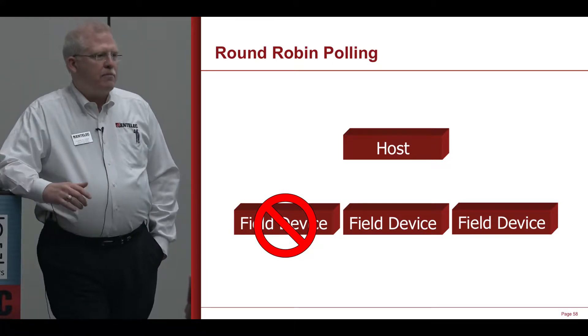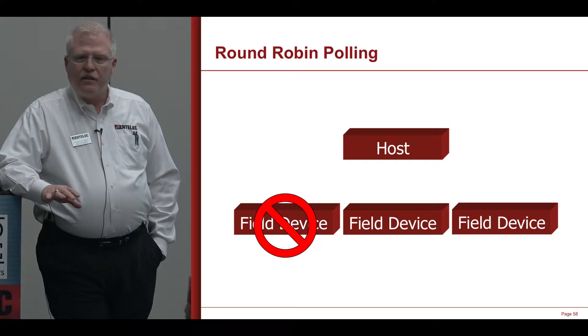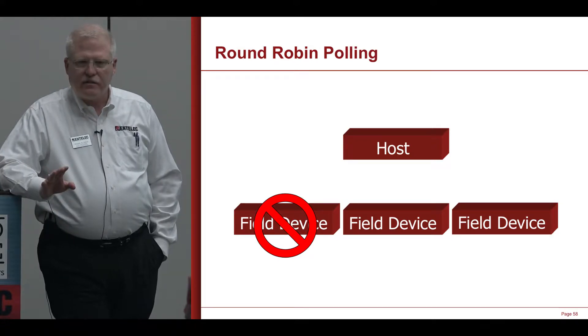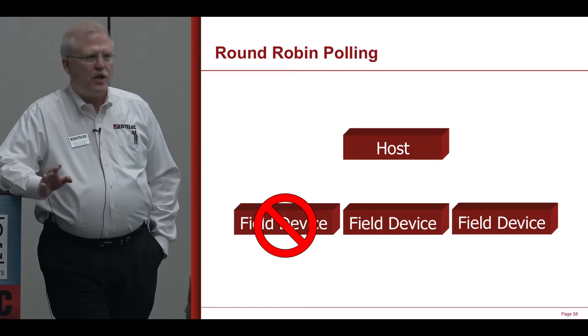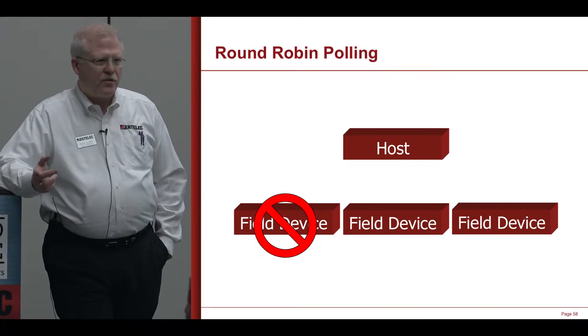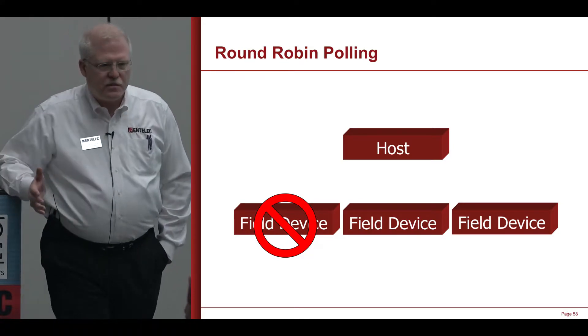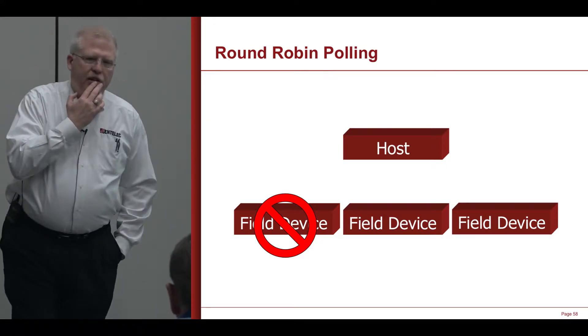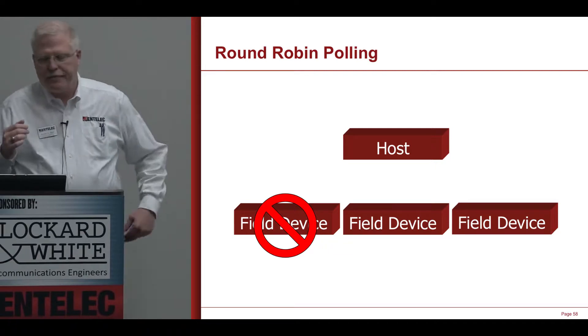Round-robin polling can be very fast if I don't have a lot of devices. If I have a lot of devices, it can be very slow — it can take 15, 20, 30 minutes to get all the way through a round-robin poll, maybe more. I've seen systems collecting wellhead measurement data where one round-robin poll takes four hours to get all the way around.